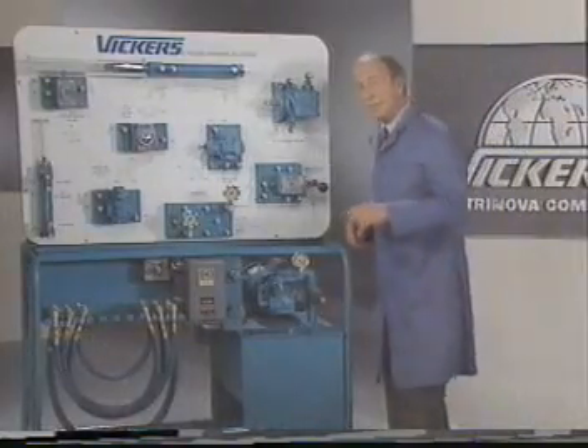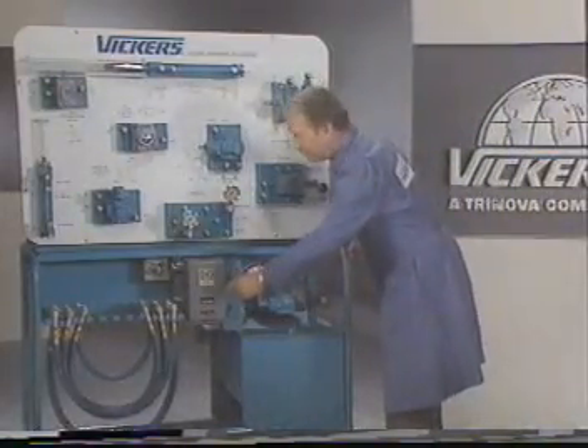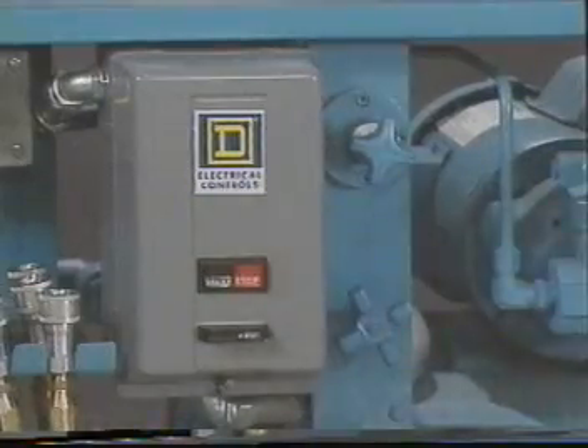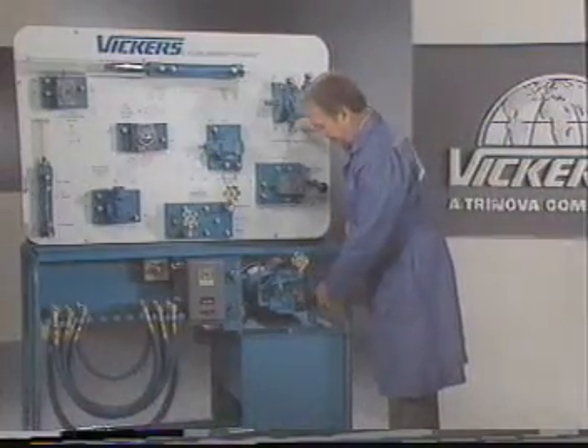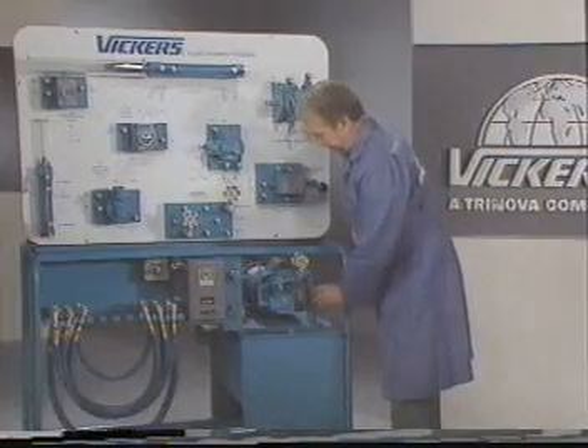Here, let me demonstrate cavitation by restricting the pump inlet. This is the normal sound level. This is cavitation.